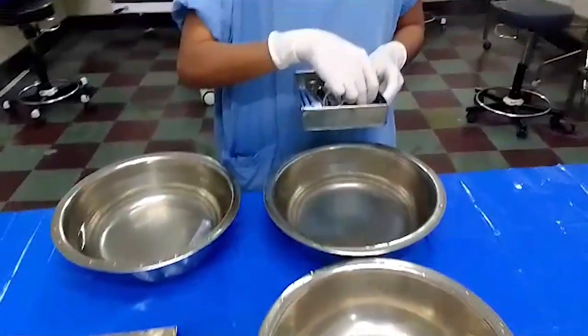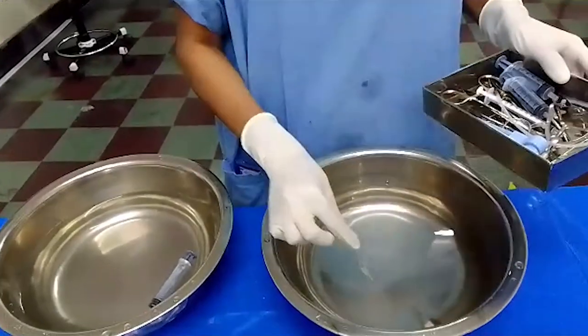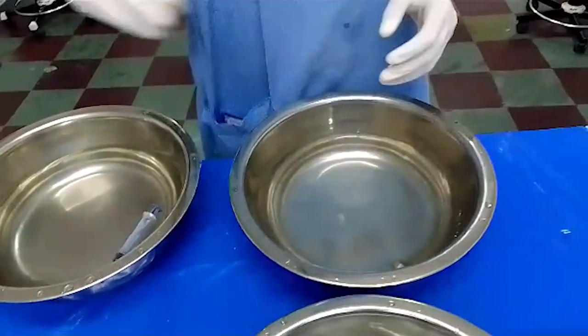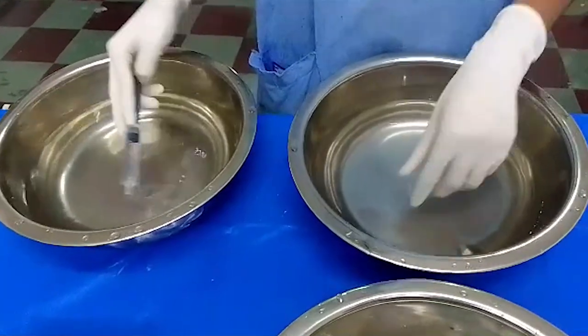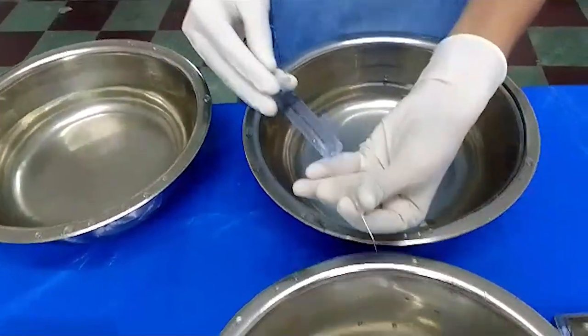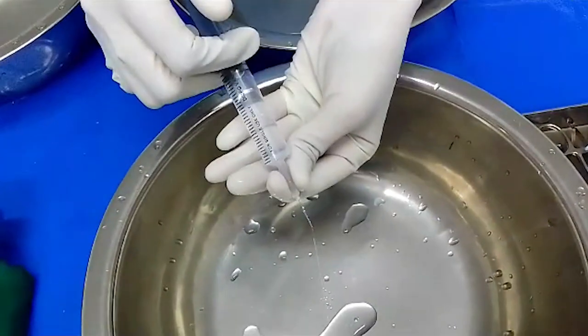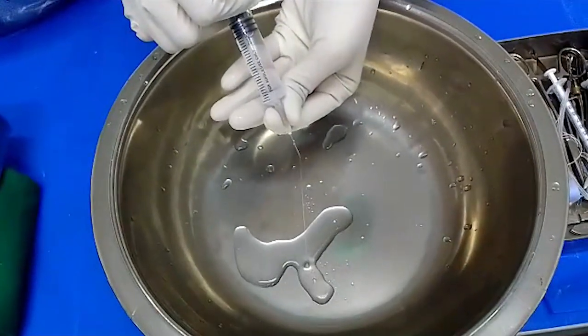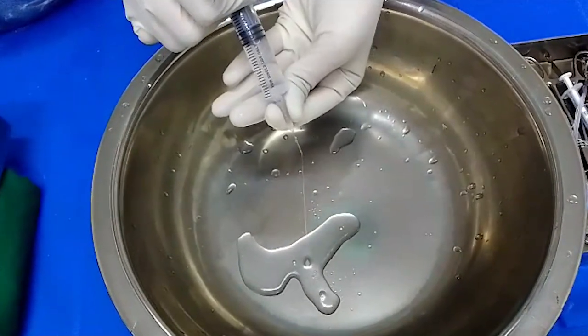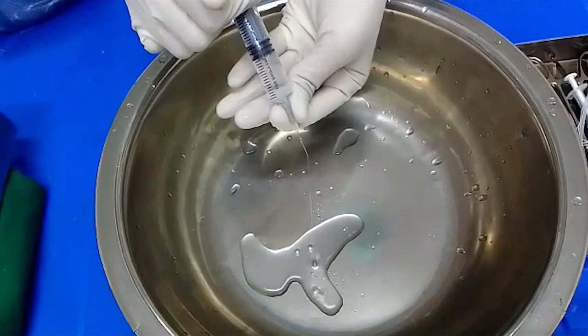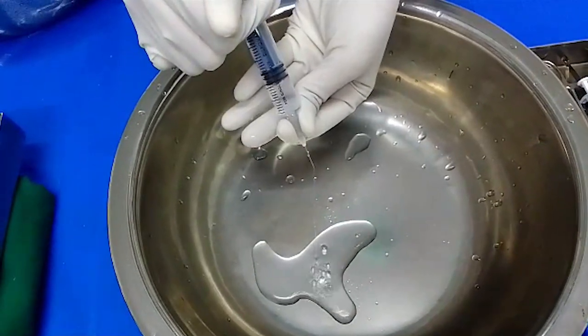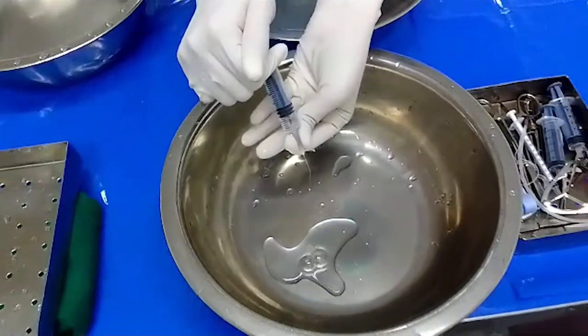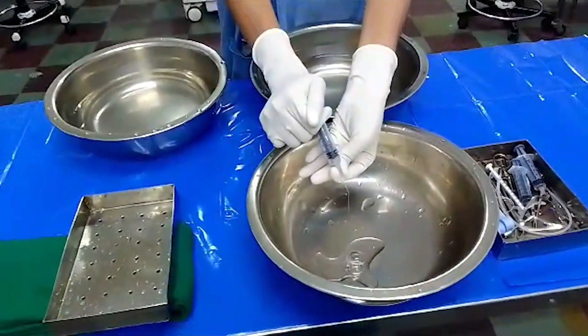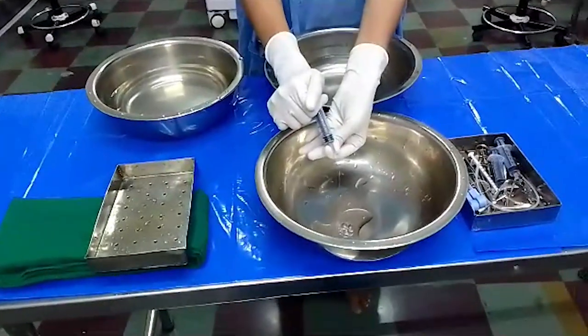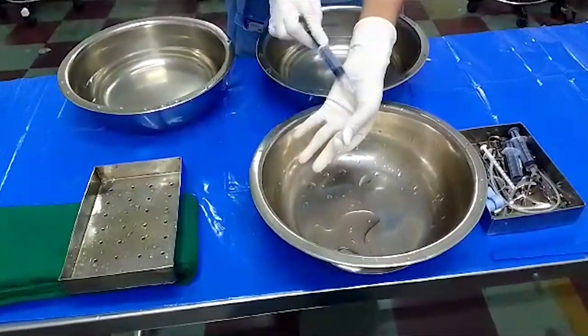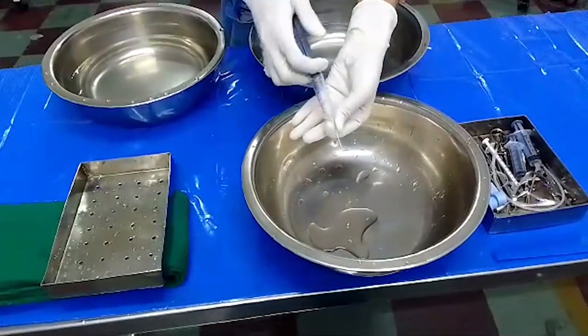So here we see that we have taken 3 basins. 2 basins are filled with RO water and we have an empty basin. Take RO filter water from the second basin and wash the hydrocannula. The entire syringe should be flushed through the hydrocannula into the empty basin. Then the syringe and the cannula are washed with air.